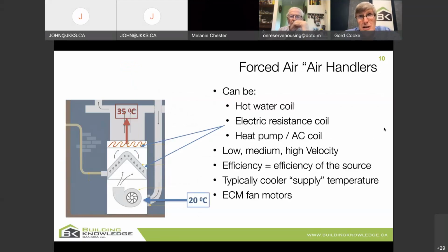What I was suggesting is that rather than, in a community without natural gas, it would be quite possible to put in an air handler, a forced air system, with an electric resistance coil -- you'll see that squiggly line on the drawing. Or you could use a hot water coil instead. So if you didn't want to use a gas furnace, but had availability of propane or natural gas for your hot water, a tankless water heater can drive hot water through these systems. Now you have one fuel, one vent that's using hot water both for showers and cooking, and also to heat the house. It's a pretty nice, fairly straightforward technology that requires a plumber rather than a gas fitter -- though you'd still have to put in the gas appliance. Or again, I could go simple electric.